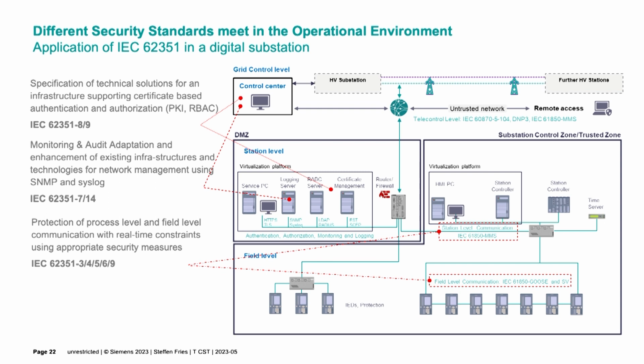Then we have the different parts that target secure communication, relating to the field level communication down here. Protocols like GOOSE or sampled values are used here, over multicast Ethernet, to ensure very timely communication.